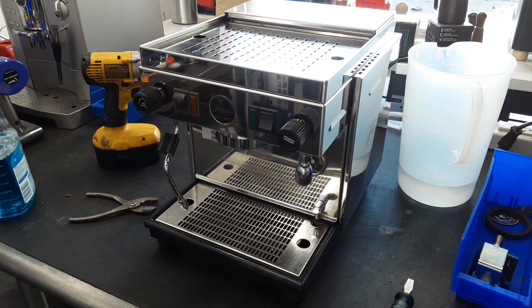As I descaled, it got worse and worse, so I quoted for some extra time to continue, because after spending no more than about 4 hours descaling, it was still coming out pitch black. Usually that's residue built up at the bottom where the heating element is, or the top of the boiler where the water doesn't reach. I kept descaling, quoted a little more time, just an hour on top of the original estimate, and we ended up getting it clear.